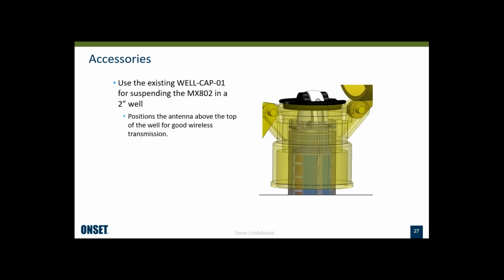And moving on, the MX802 logger was designed so it could be mounted in the same well cap that we've been selling for the MX2001 loggers. So this attaches to the top of 2-inch wells. And this well cap is designed to hold the top of the logger high enough above the well, if it's like a metal well, so that you get good Bluetooth communications through that well cap to offload the data without having to even pull up the logger.